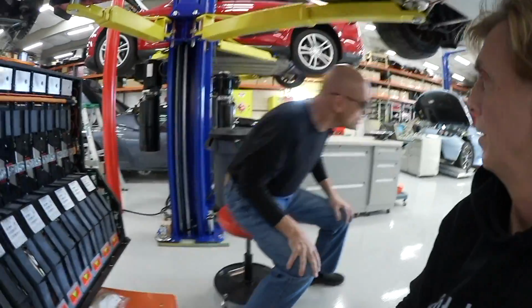We actually have special battery maintenance devices that will degrade a brand new battery, or age it, to match what's already in the string. Otherwise, the other batteries really take a beating when you put new batteries into a string, because they're putting a load on it in order to reach that level. There has to be some equilibrium.